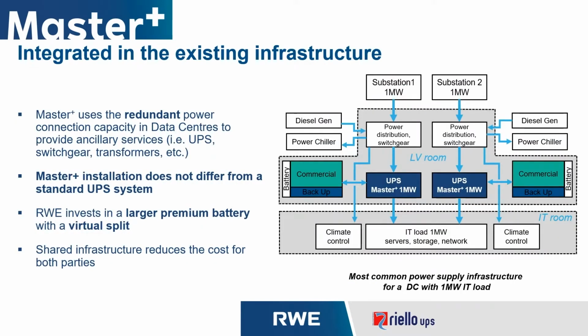One of the key benefits of the Master Plus solution is that it can be integrated into an existing infrastructure. Now the Master Plus can effectively utilize the redundant power connection capacity of most data centers. The Master Plus installation effectively does not differ from any other standard UPS system. The benefit of this is RWE invests in a large premium battery with the virtual split, and shared infrastructure reduces the cost for both parties.